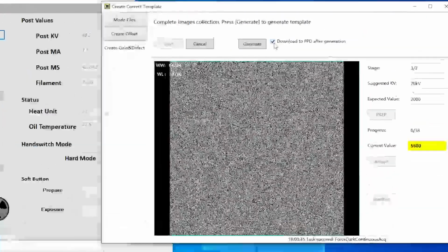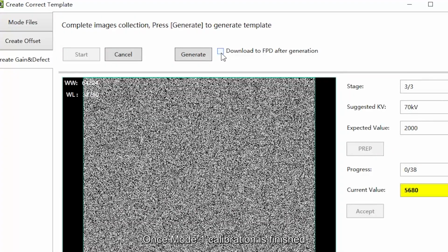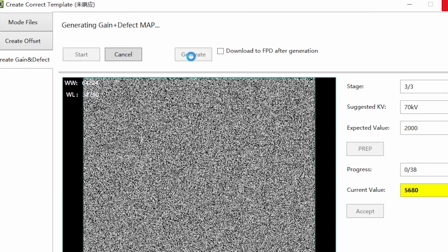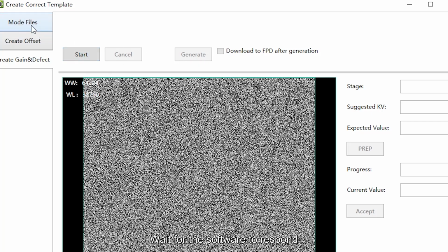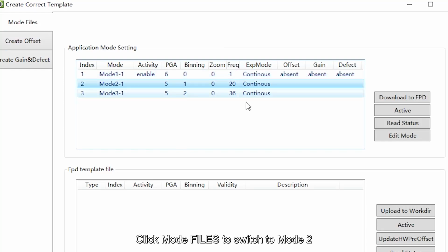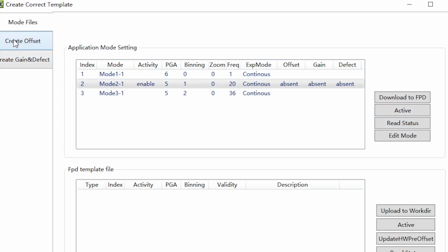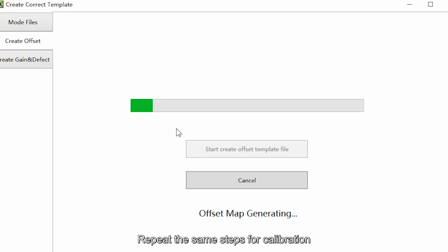18. Dynamic Tablet Calibration 4. After completing the flat panel calibration, once Mode 1 calibration is finished, uncheck Download. Select Generate to save. Wait for the software to respond. Click Mode Files to switch to Mode 2. Repeat the same steps for calibration.